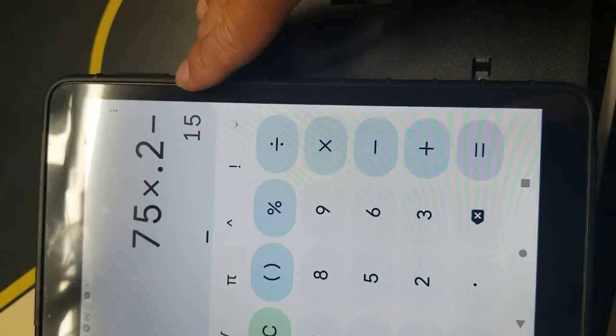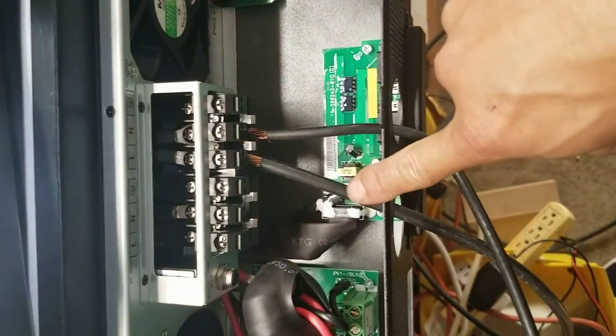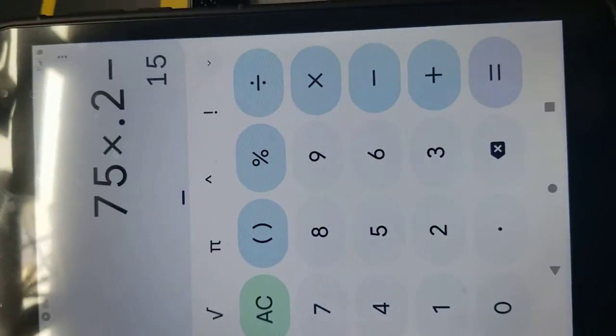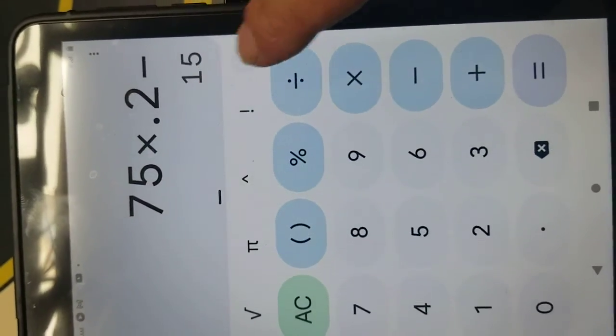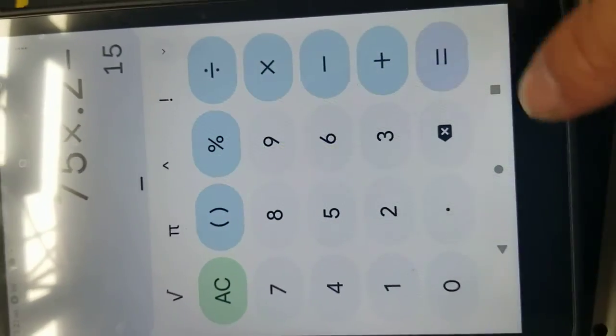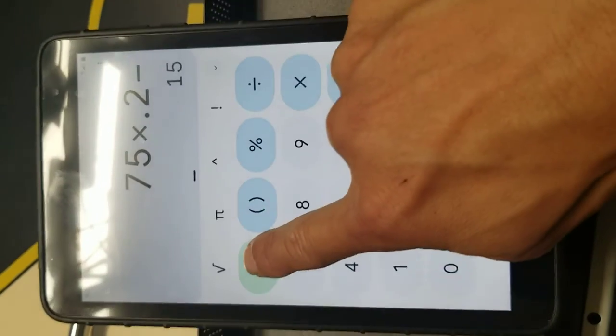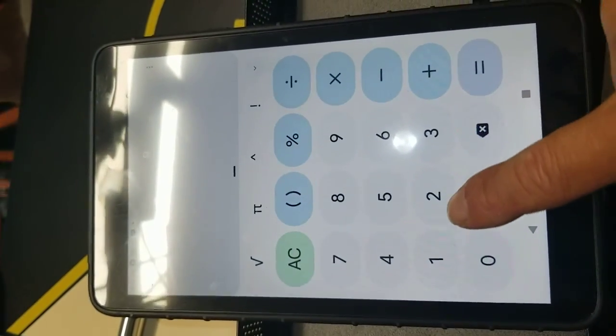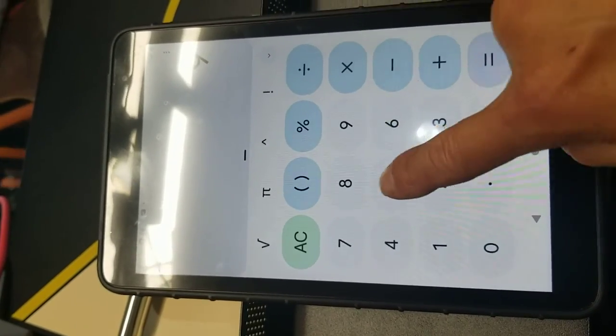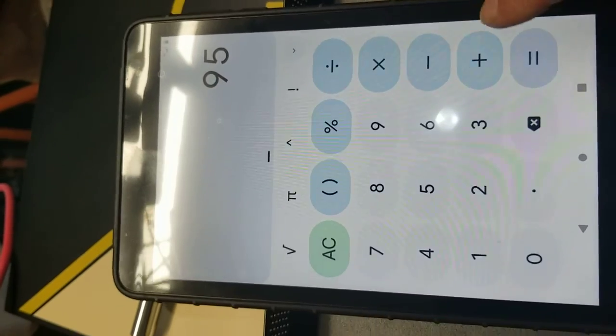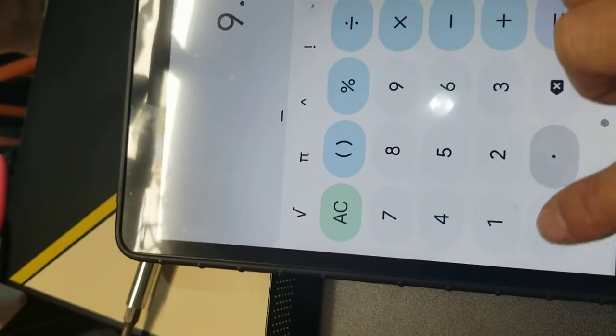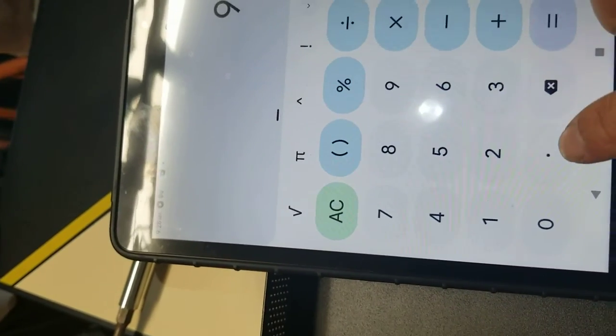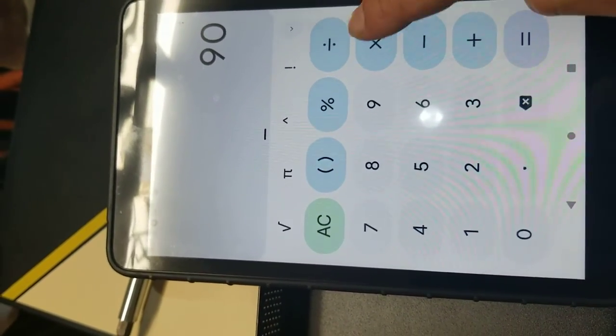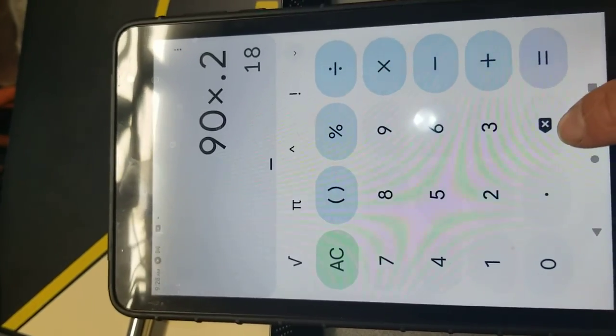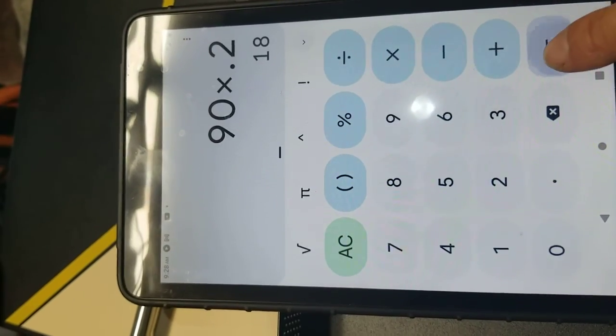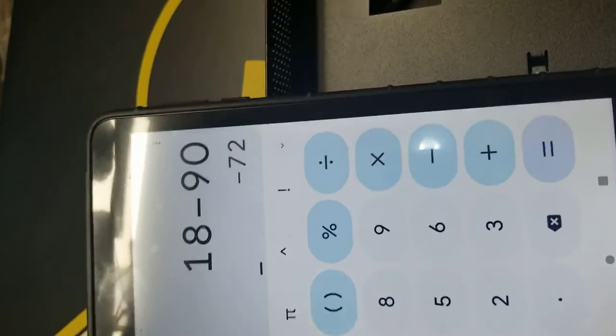But you guys can buy the 4 gauge, which is 90 or 95 amps. Let's say 90 amps — I forgot exactly what it says, I think it's 95 or 90. Let's say 90 amps multiplied by 0.2, which is 20%, that gives you 18. So 90 minus 18 gives you 72 amps.